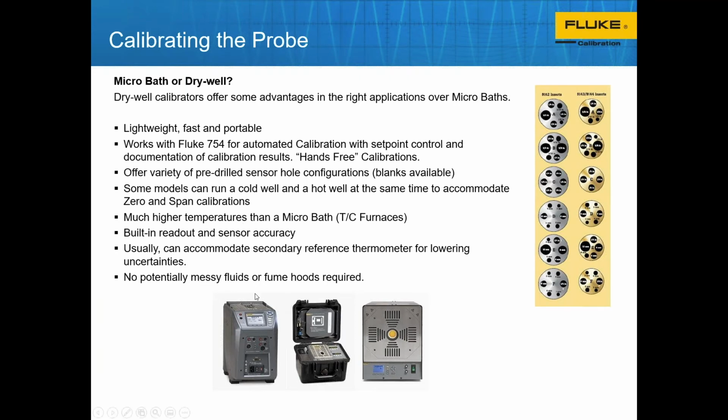Comparing them directly to baths, there are some pretty obvious differences. A lot of times the fluids that are used in baths can be silicone fluids. They are prone to potential contamination. They also might off gas, so you need to have fume hoods installed. This is the type of lab equipment that typically doesn't see the field. So that's where a dry block comes into play.